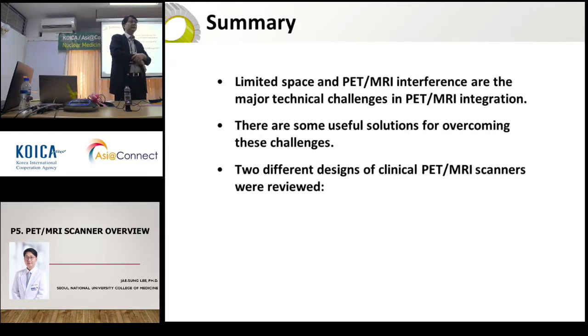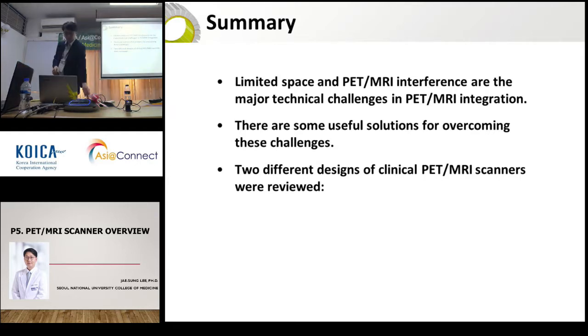I have one question. In the simultaneous data system, how is the interference of the MRI magnetic field on the photomultiplier tube electrons removed? Based on the PMT? Yes, if the PET system is based on the PMT, simultaneous scanning would be almost impossible. That is why in the Philips system they use separate gantries. Some RF shielding would be useful, but it is not sufficient for reducing all of the interference. So that is why they need separate systems.